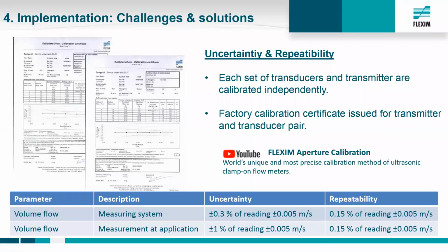Just a small teaser, if you like this presentation and afterwards you want to see how we calibrate our systems, there is a very nice short clip on YouTube available. Because we are doing also the wet calibration rig, as most of you I guess are aware, on a wet calibration rig, but we have also aperture calibration. It is a very unique transducer calibration for clamp-on ultrasonic flow meters, and I would like to recommend this short clip to you to get an impression of how we do it, what is so unique about it, and why it is a nice way, a smart way, to calibrate.